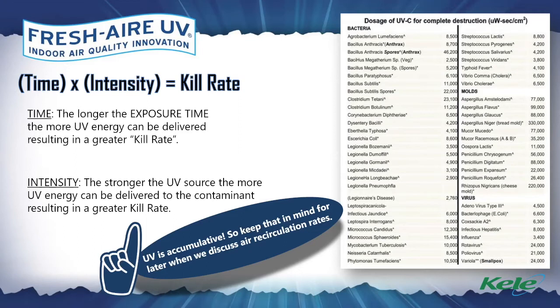So for example, if we want to address Legionella, which we're all familiar with, certainly could be an issue in drain pans, stagnant water, you require about 3,000 microwatts of UV energy dosage for inactivation. If we look at Aspergillus niger, which is also found in the coil section, if you look on the right side of the column under molds, that requires 330,000 microwatts. So we have a pretty varying degree of dosage requirements for a very weak Legionella and a very robust Aspergillus niger. So when a UV system is designed and implemented, it is so important to have an understanding of what it is we want to address and deliver the required dosage requirements in order to achieve that inactivation rate.